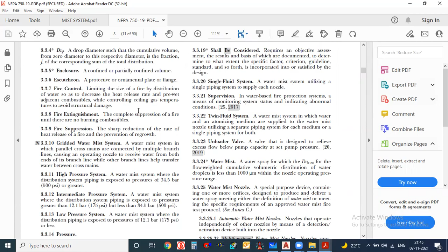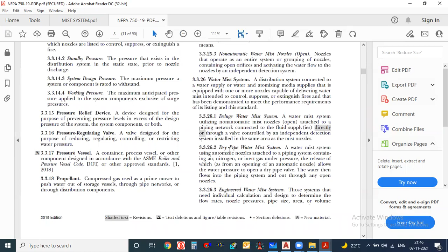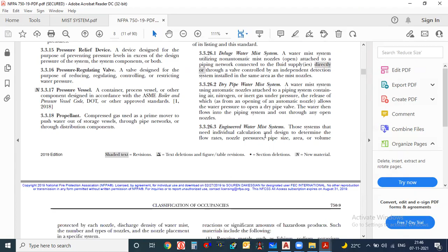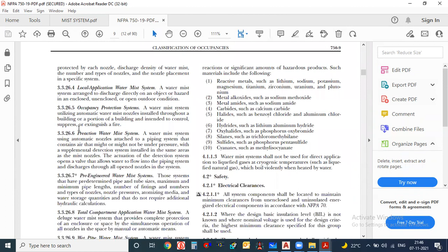Here they have given types of water mist system. That means water mist system can be attached with a deluge valve also. Just remember, whenever we are talking about deluge, the meaning of deluge system is that all the sprinkler heads are open. So water mist system can be attached to the deluge system. It can also be attached to the dry pipe system. Dry system means there will be one control valve which is controlling the system. In case of fire, then only the valve will open and water enters into that particular system.